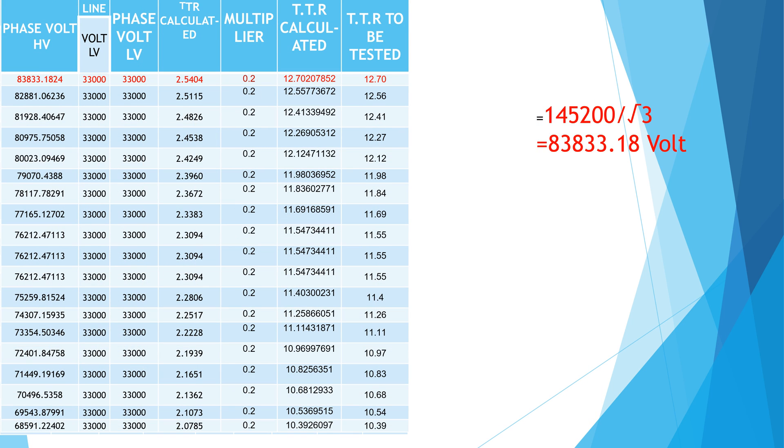In delta side voltage is 33 kV. Here phase voltage is equal to line voltage. So ratio of voltage is equal to 2.5404 at tap number 1.